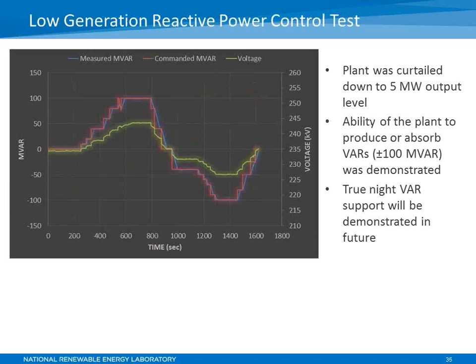This is that low generation, or close to zero power, voltage control test I mentioned earlier. So again, this time series shows that at very low power levels, in this case, the plant was curtailed to only 5 megawatt level. And by the way, this test was done when a couple of hundreds of megawatts were available from solar radiation. The reason we didn't do a nighttime control test was based on the logistics of this experiment.